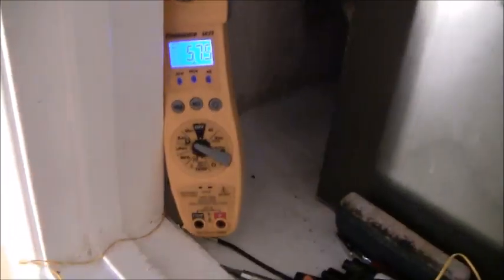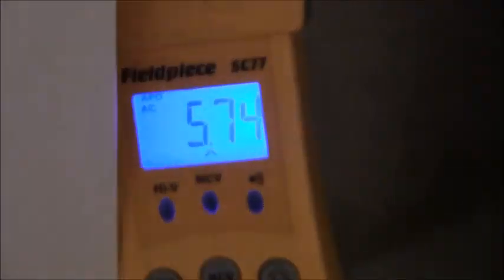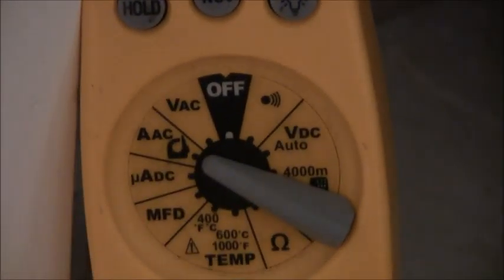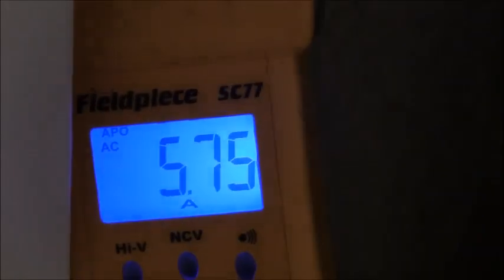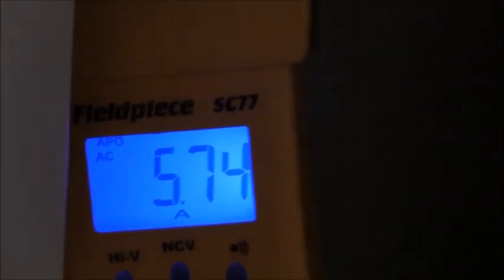And there you go. This should be feeling nice hot air, which I do feel, indicating that the condenser is rejecting the heat, which is what it's supposed to do. So let's go inside and check the unit. Wow, look at this. We're getting 5.7 amps on that supply fan. Amperage AC, 5.75. So this unit is pulling more when it is in cooling. Let's write that down, 5.75.